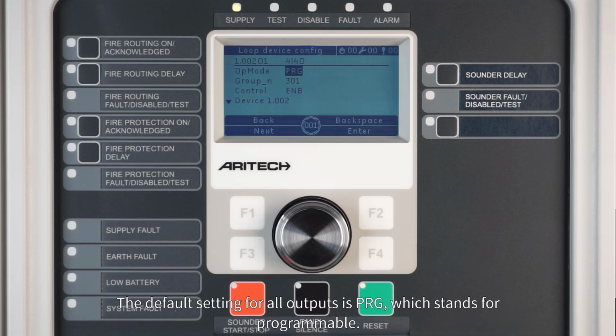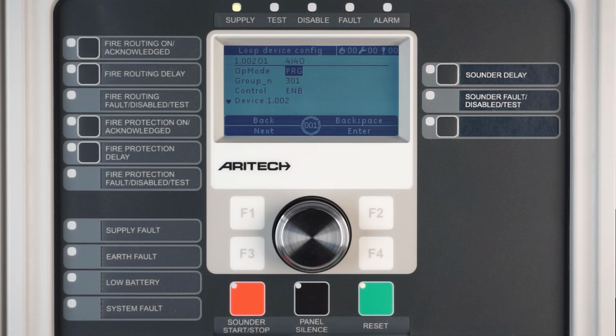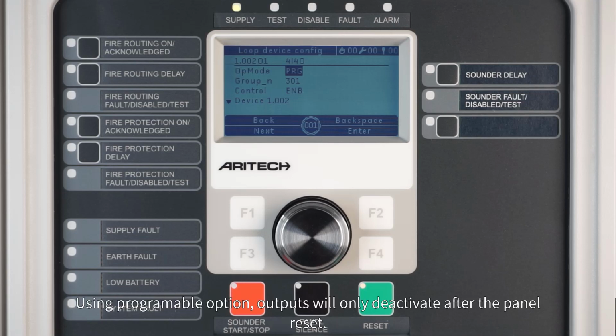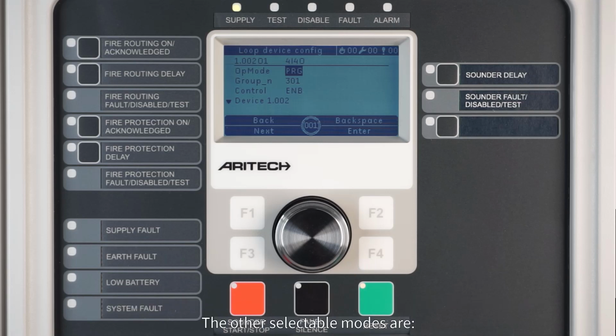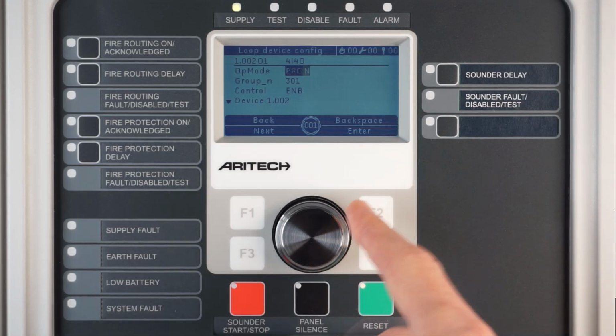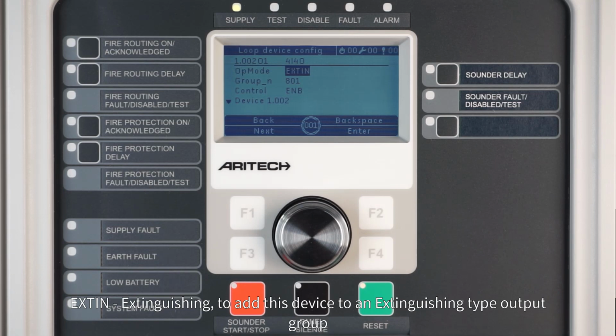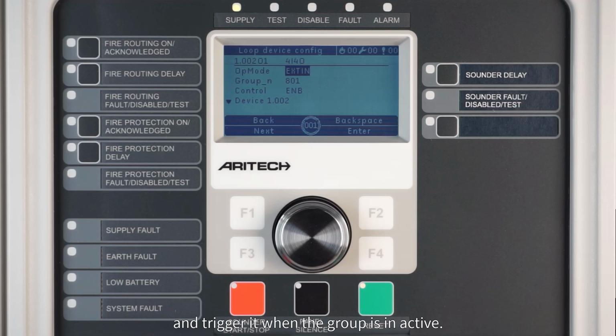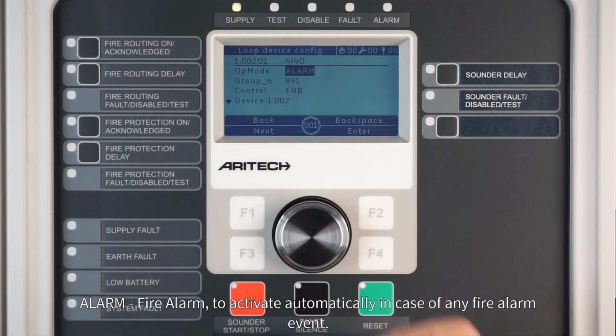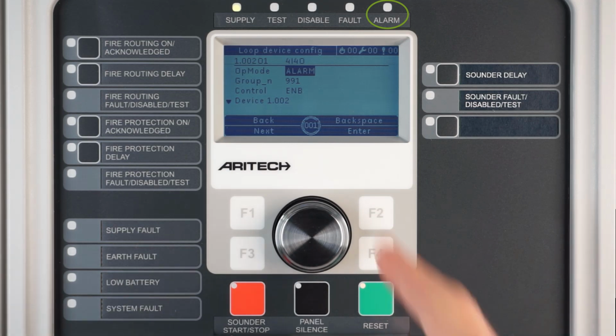The default setting for all outputs is PRG, which stands for programmable. Using the programmable option, outputs will only deactivate after the panel reset. The other selectable modes are extinguishing, to add this device to an extinguishing type output group, and trigger it when the group is active. Fire alarm, to activate automatically in case of any fire alarm event.